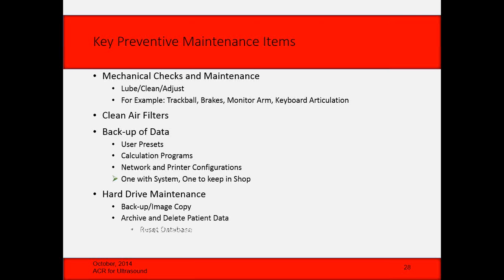And then hard drive maintenance. Some of the systems have utilities for resetting the database that completely clears it out. It's a really good idea to do that on a regular basis. Some of the user manuals actually say they should do it every 2 or 3 days, or even daily. GE says do it daily. So that's an important step to keep the hard drive from getting corrupted. And then on some systems, making an image copy of the hard drive is an important item.